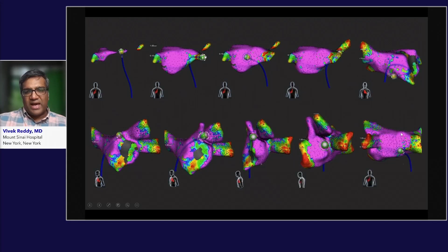This is also a mapping system. So as you sweep the catheter around inside the chamber, you can render the anatomy as well as annotate electrical information, such as this bipolar voltage map. During the mapping, again, there's 9 surface electrodes and there's a central reference. So what you're talking about is really close unipolar configuration. This reduces far field potential. So you can create electroanatomical maps.